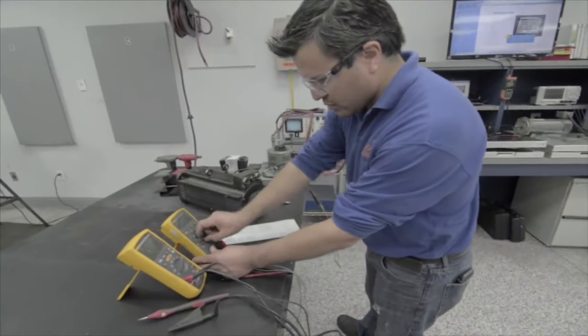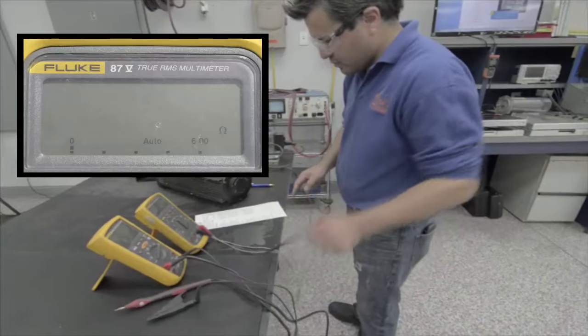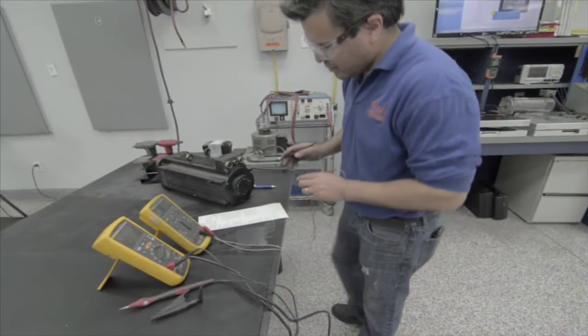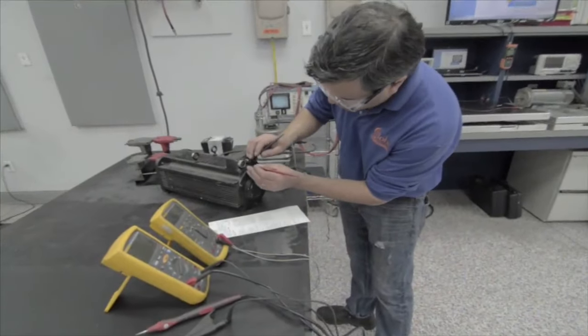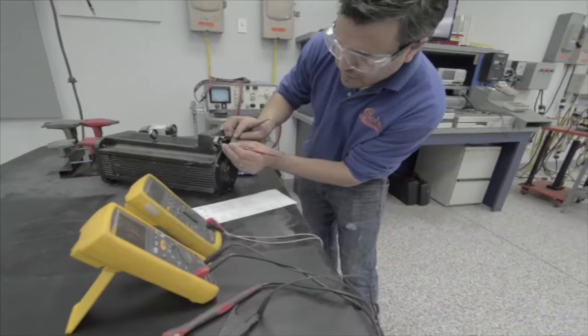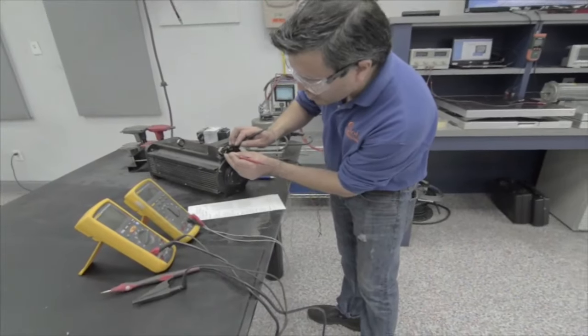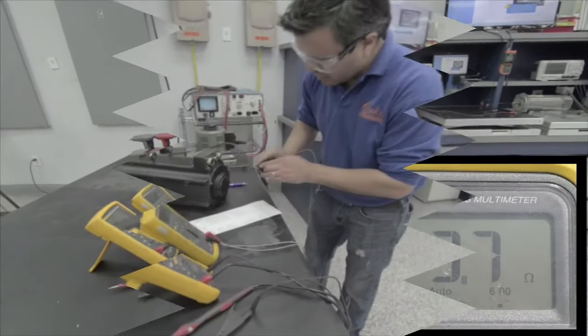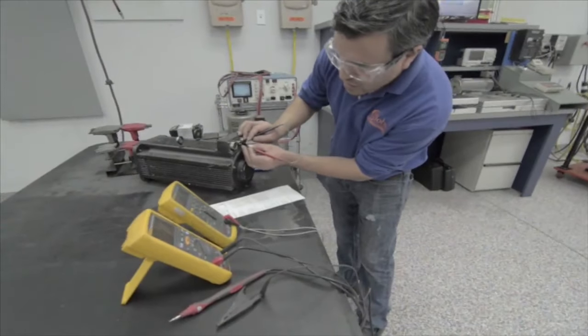A winding resistance phase balance test using a true RMS meter is now being done to check and make sure that the windings are balanced. Next, in between the phases, phase one to two, phase two to three, phase three to one, we'll also get a reading on the coil for the 24-volt brake. Looks good as well.